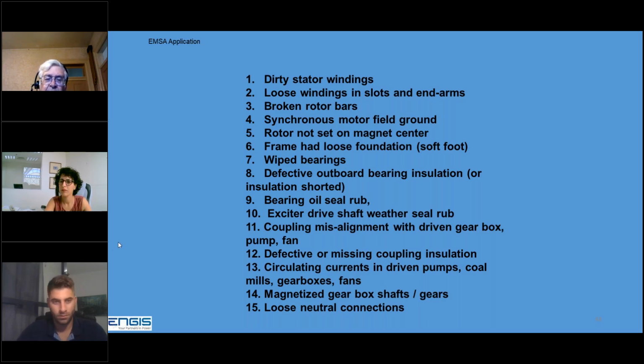Seal rubs on an exciter of a big synchronous motor, pump motor. Coupling misalignment I talked about earlier. And this can also be in a gearbox for a fan or a pump. Coupling insulation missing, circulating currents in the pumps, the mills, the gearboxes, the fans. Often they do not demagnetize gears in gearboxes. So if you have a rotating magnet, you produce current and this will chew up the gears. We found that in many steel mills.